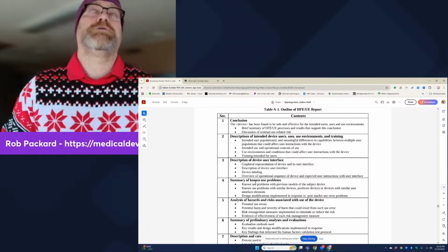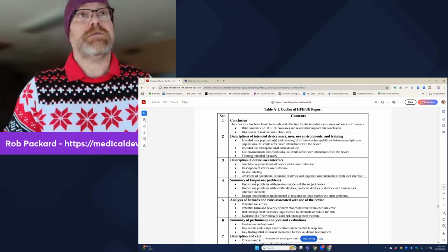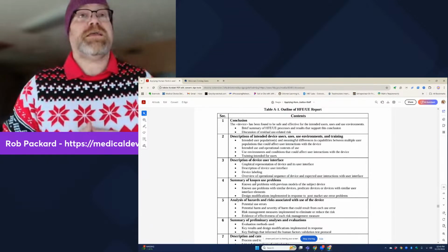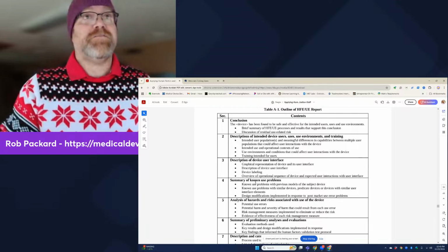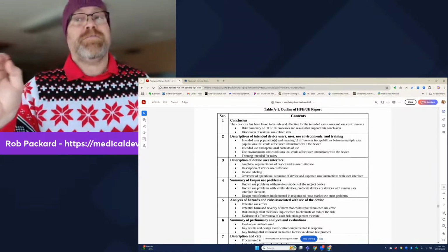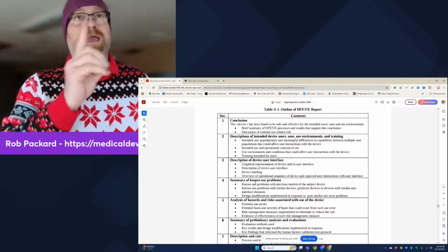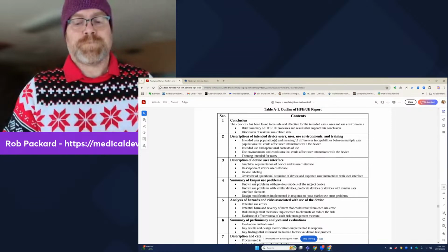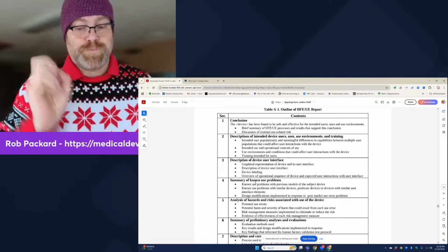And you say, oh, this is going to be so long. Yeah, it's probably going to be a 40-page report. Yeah, that's what the FDA expects. Give them what they expect. Give it to them in the order they want. Give them exactly what they asked for. And follow my tips, and it won't take you quite as much work as you think. Okay, so that was trick number 2.